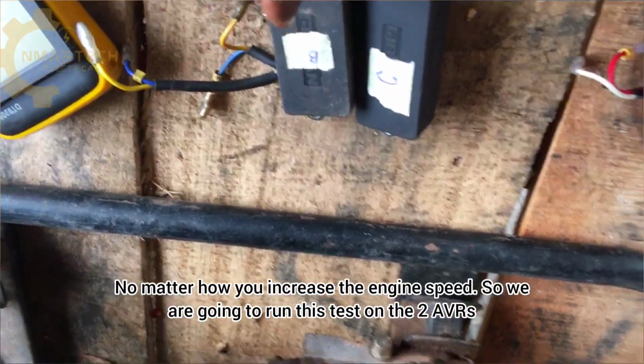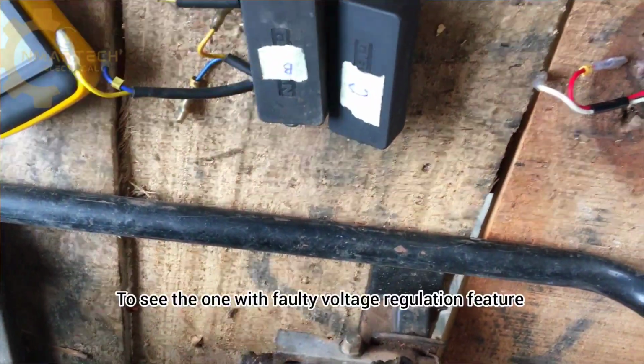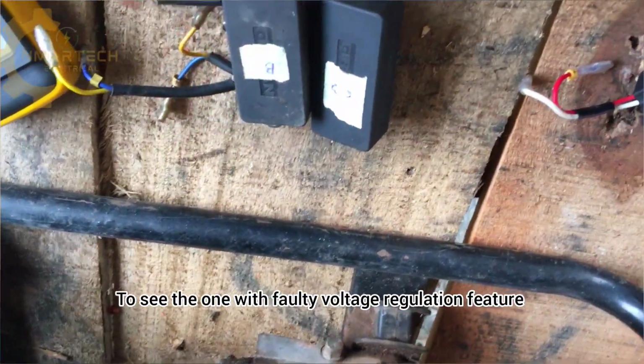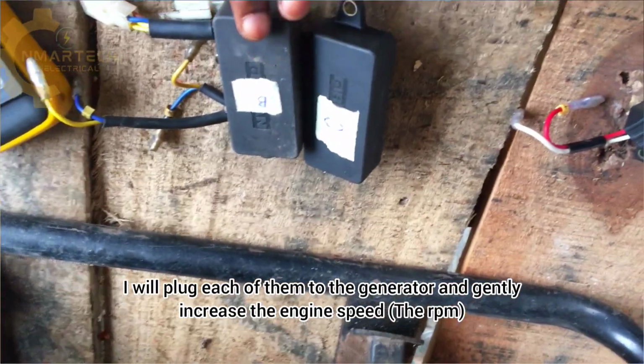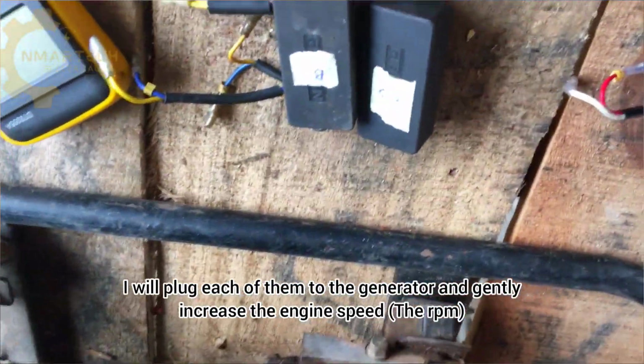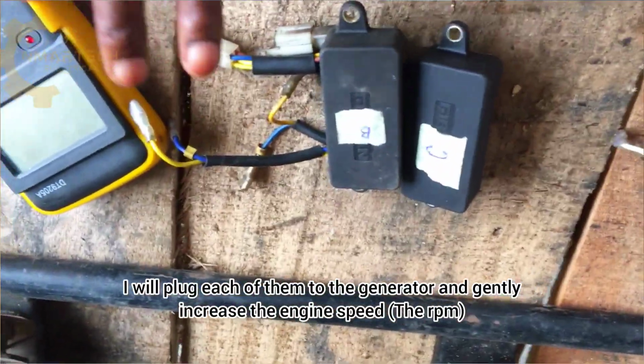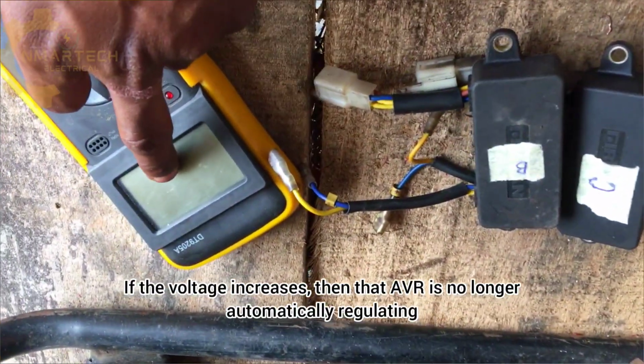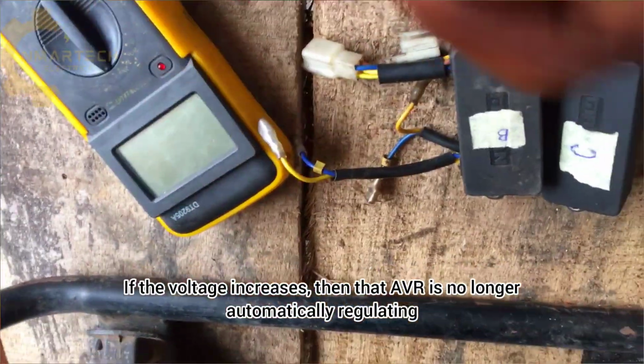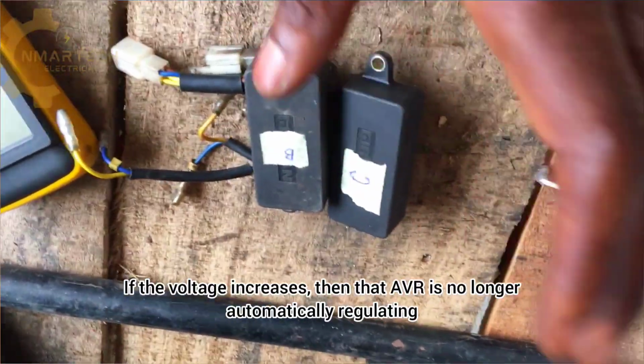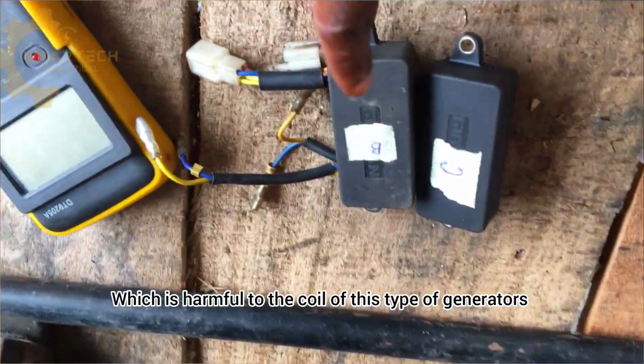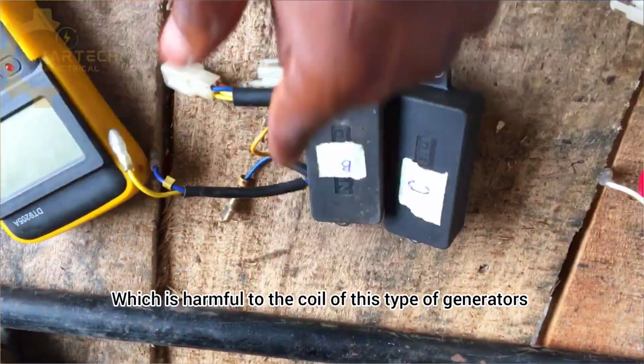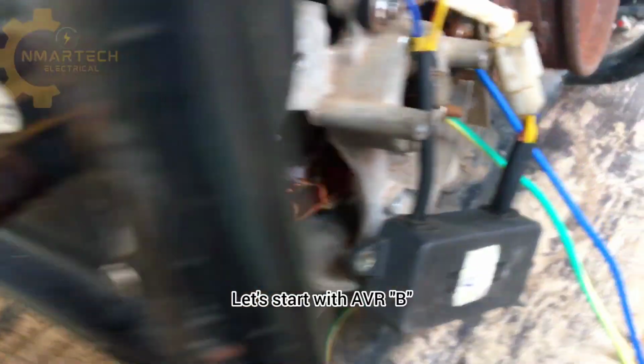So we're going to run this test on these two AVRs to see the one with the faulty voltage regulation feature. I will plug each of them to the generator and gently increase the engine speed, that's the RPM. If the voltage increases, then that very AVR is no longer automatically regulating, which is harmful to the coil of this type of generators. Let's start with AVR B.